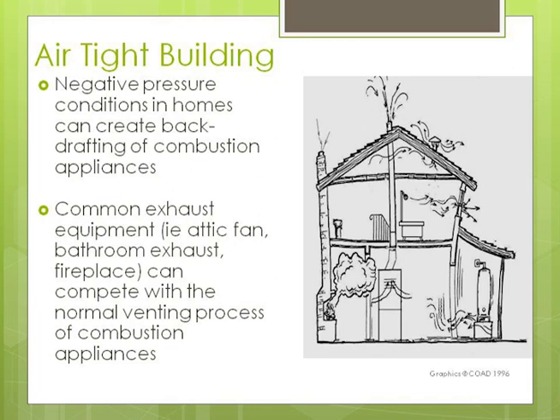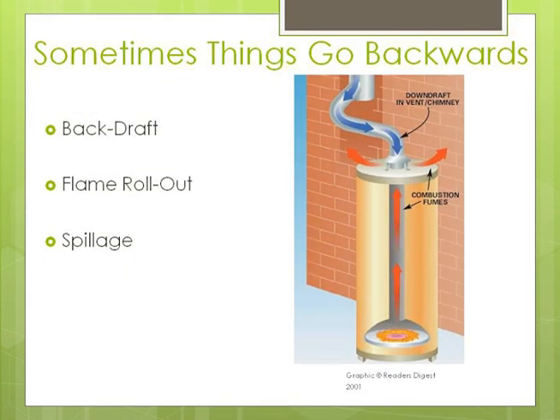If you want to ventilate your house using bathroom fans or a whole-house fan that only pulls air out, you're going to run into problems if you have combustion equipment like a fireplace, an old furnace, or an old water heater. Back draft is when an atmospherically drafting flue has so little pressure in the room that it pulls air backwards, so all the combustion fumes go into your home where they can harm people.